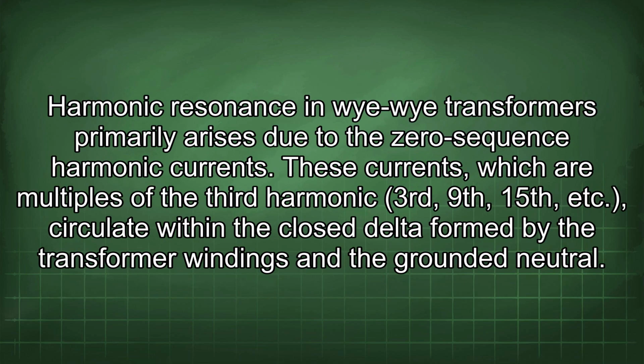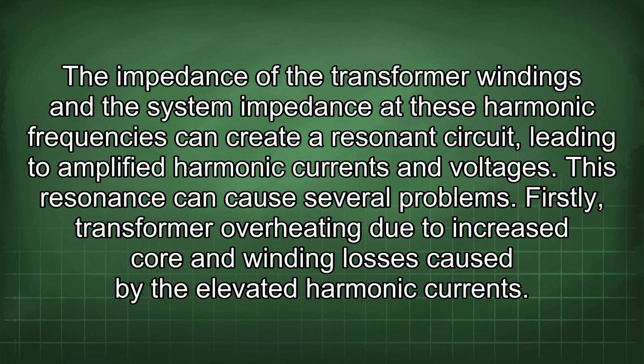Harmonic resonance in Wye-Wye transformers primarily arises due to the zero-sequence harmonic currents. These currents, which are multiples of the third harmonic (third, 9th, 15th, etc.), circulate within the closed delta formed by the transformer windings and the grounded neutral. The impedance of the transformer windings and the system impedance at these harmonic frequencies can create a resonance circuit, leading to amplified harmonic currents and voltages.